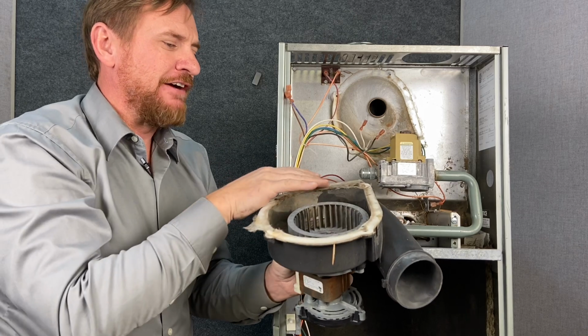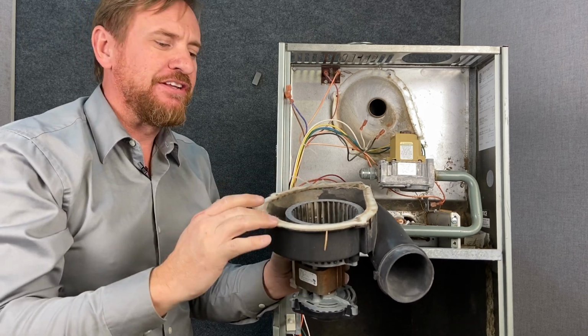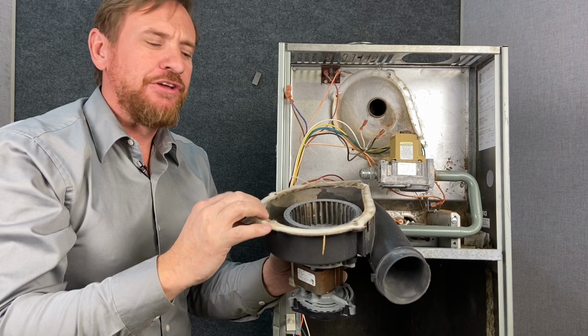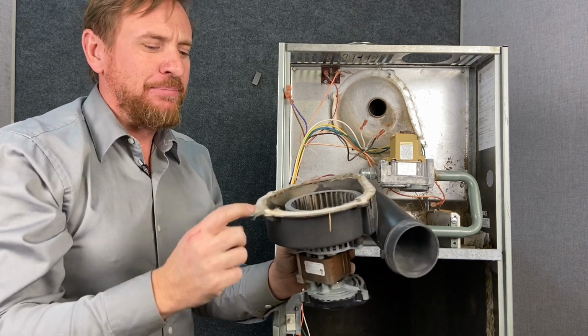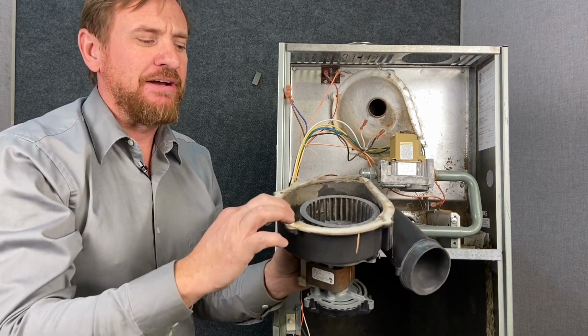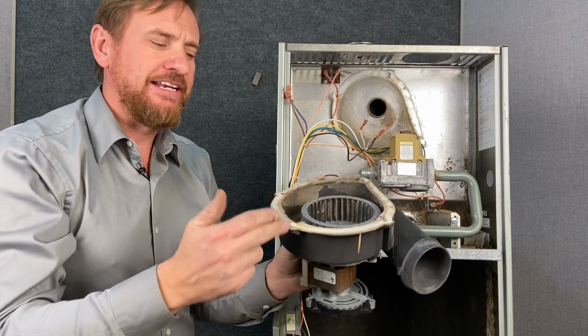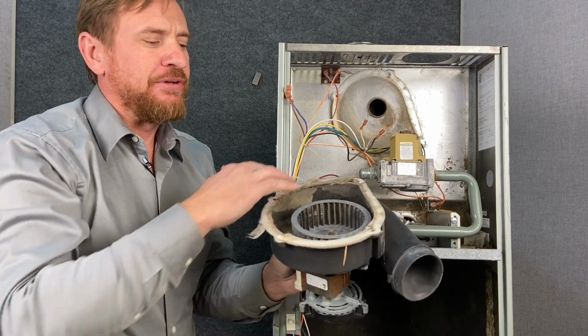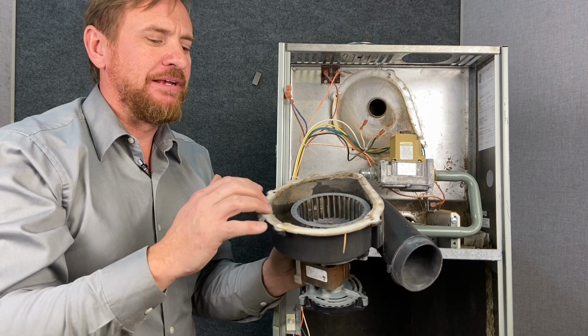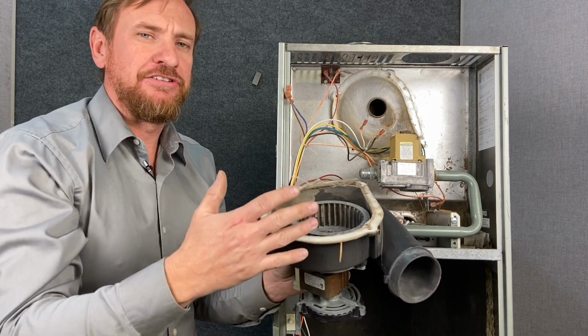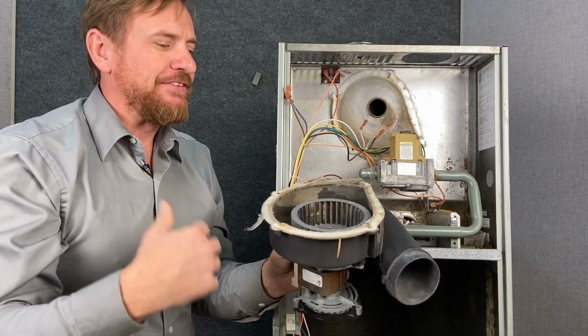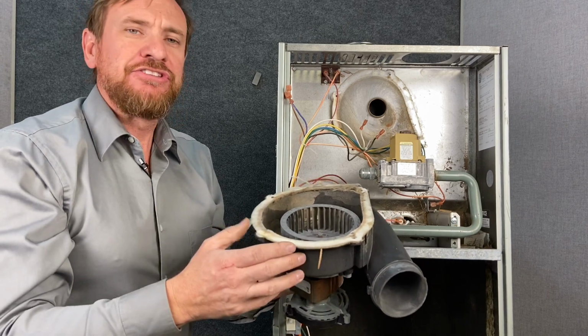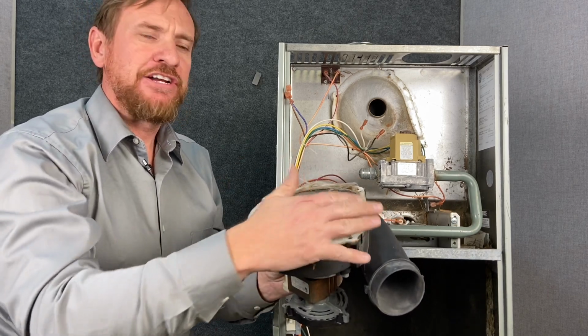If you're going to pull this off and reuse it, you want to be very careful that you didn't damage it, or be prepared to have another replacement gasket in. So if I put this back in with this big tear right here, it could be pulling air through the side here and not protecting it. You also can't use any kind of rubberized because the temperature of this could be very hot and it could cause it to melt. There's a lot of what ifs, high temperature this and that. You get into lots of gray areas. I like to go back with what the manufacturer designed.